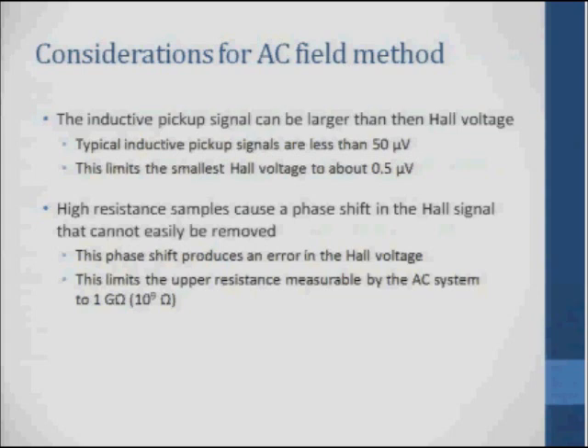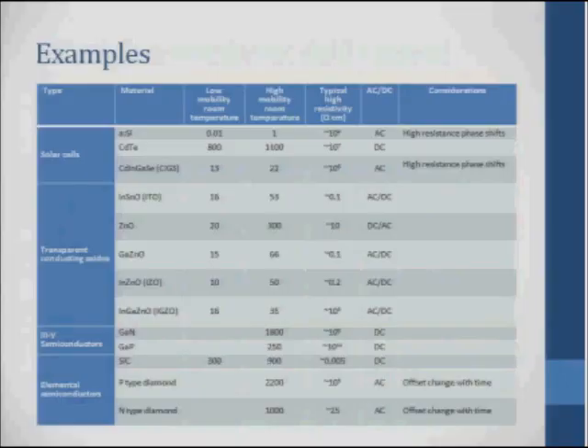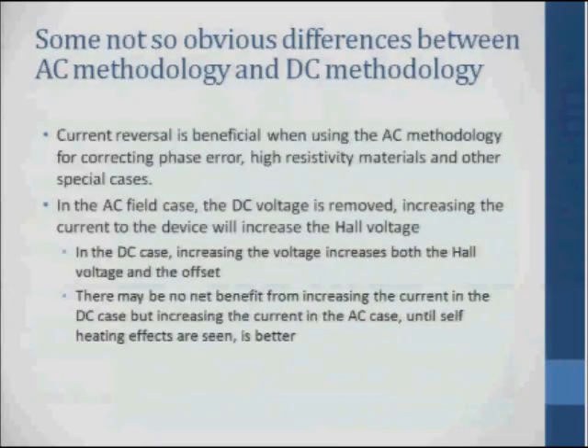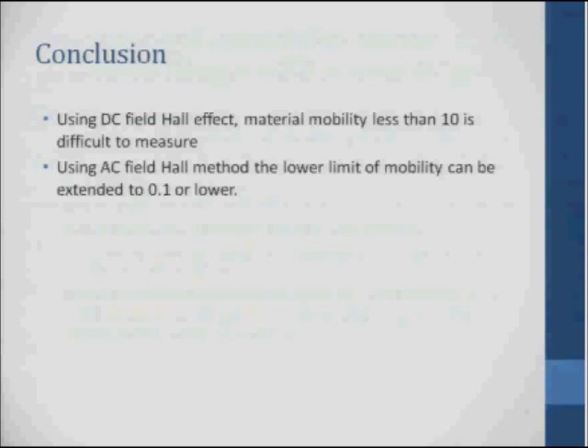In this current design, the practical limit for the Hall voltage is about half a microvolt — the limit we think we can reliably measure. High resistances cause a phase shift that cannot easily be removed; this produces an error in the Hall voltage and limits the resistance of AC systems to something around a gigaohm. We can build a chart of common materials and whether AC or DC is the appropriate method. In conclusion, for materials with mobility less than 10, DC Hall effect is difficult; the AC Hall method can extend this down to 0.1 or lower.